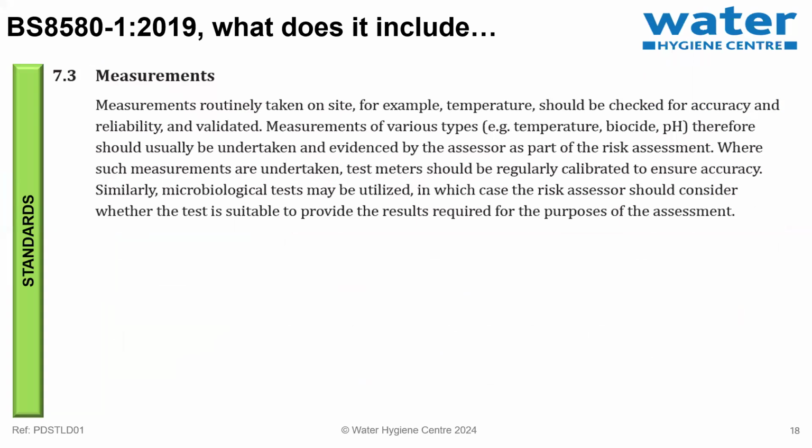There are different types of thermometers, for example. There are immersion, contact, dial gauges on vessels, dual probe gauges on vessels, BMS systems. Do they know how to use them correctly and where to record the data? Were the probes calibrated? When was the last time the temperature probe was calibrated? When was the last time we calibrated a gauge on a vessel, for example? And how reliable is this data?